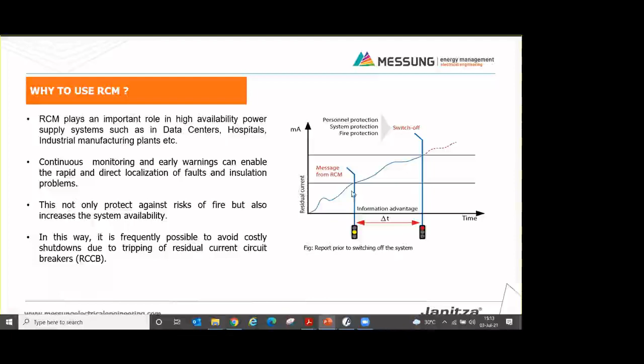For example, in this case, I have set 2 limits. If my first limit is exceeded, then I will get a warning. This is the traffic signal indication, which will quickly tell us the status of our system. So I will get a warning that my residual current is increasing beyond this limit. Once it exceeds the second limit, then it will take the necessary actions according to the set logic. So this is the benefit which we will get from the continuous monitoring.